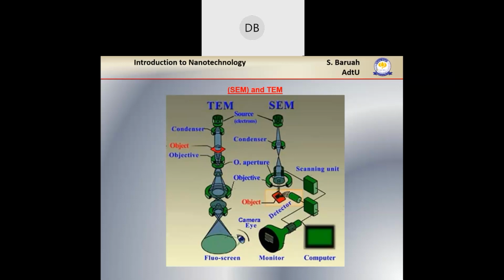Finally, using these converging lenses, which again are electrical lenses and not optical lenses, we can converge the electron beam and get a very small spot size. Spot size means the circular spot at which it hits the sample, which can be somewhere around 10 nanometers or even less, 5 nanometers, 2 nanometers. That is our primary probe. So the primary probe hits the sample. I'll talk about what the secondary probes are later.